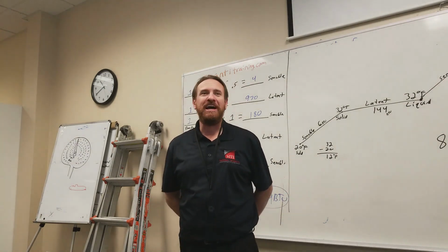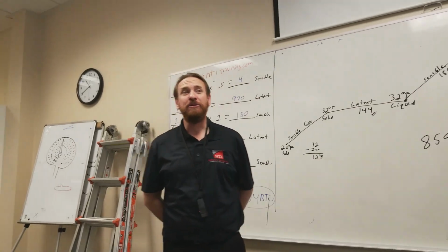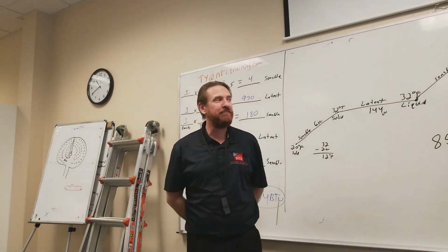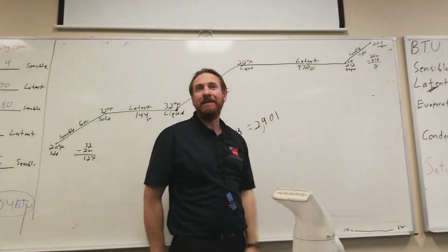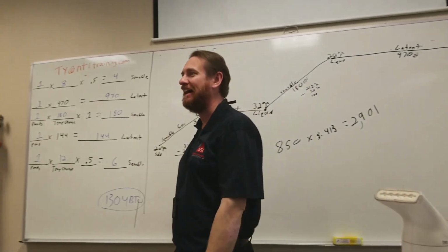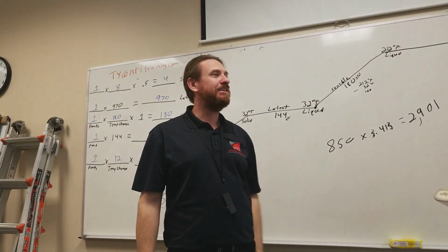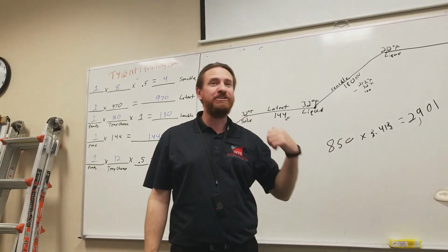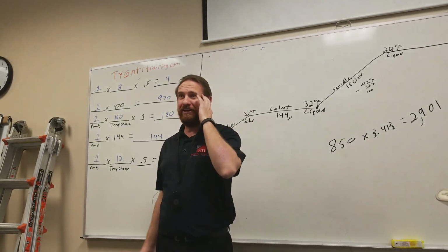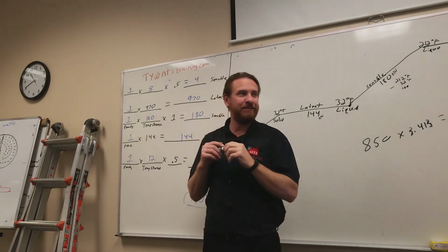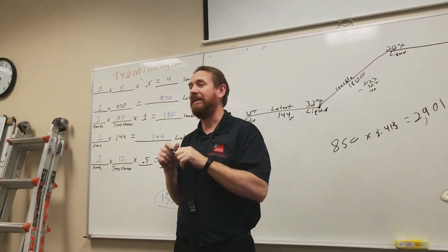So when we pull water out of the air, can we measure how much water we're taking out of the air? Yes, we can measure it in gallons or really pounds, right? So for every pound of water I want to pull out of the air, that's 970 BTUs of heat energy that my air conditioner has to have of capacity. And I got to reject that outside in the condenser. So I got to pull the heat in the evaporator, inject it into the condenser outside. So in Florida, it's very easy to pull out 5 gallons of water in a day. You can fill a 5-gallon bucket in one day from your air conditioner.